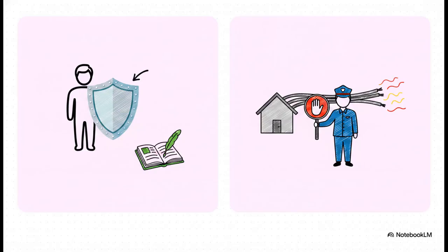So, the absolutely crucial takeaway here is understanding the difference between these 2 components. They really are a tag team of safety, but they do completely different jobs. The RCD protects you, the human, from deadly electric shocks by looking out for those tiny imbalances. The MCB, on the other hand, protects your home's wiring from melting or starting a fire by monitoring the total current volume. So for example, it'll trip if a 32 amp limit on your plug sockets gets exceeded.